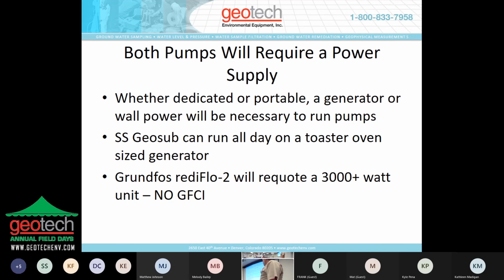Whether dedicated or portable, a generator or wall power is necessary to run the pumps. The Geosub can run all day on a small 1,000 watt toaster oven sized generator. That's kind of how I reference it, because if I've gotten a call over the years about what size generator I should use to run my pump, the rediFlo-2 always requires a much larger generator, usually in the 3,000 watt plus range. You can use a 2,000 watt if the motor lead is shorter in length, usually 200 feet or less.